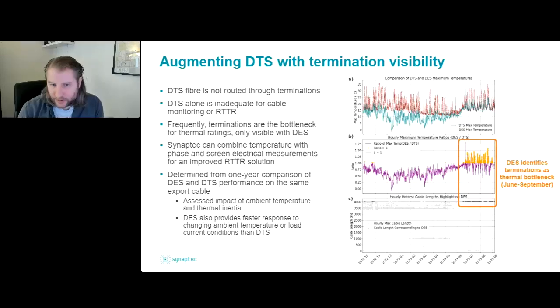What we found in this data is that, about 20% of the year, our sensors showed that the termination was the hottest point in the system, whereas the rest of the year, somewhere along the length of the cable was the bottleneck. So DTS alone gives you a decent impression of the thermal rating of the cable, but doesn't tackle the thermal rating of the terminations at each end. We're able to fill that gap and provide a solution for RTTR that's complete and gives a full picture of what's going on.